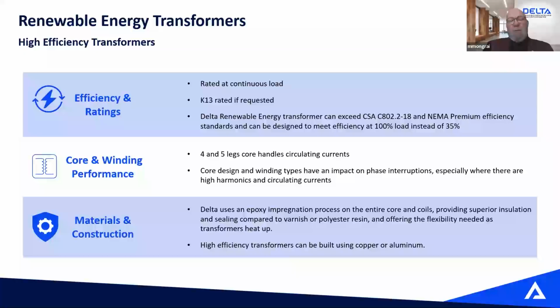The core and winding performance. So usually we're going to see a 4 or 5-legged core when we deal with YY connection. I have a few slides later on explaining this. Core design and winding type will have an impact on phase interruption. Again, this is really related to the inverter and the requirement of the inverter manufacturer. At Delta, we use epoxy impregnation of all of our transformers. I'll explain that a little bit later. And we can build transformers with higher efficiency than the minimum required by law.